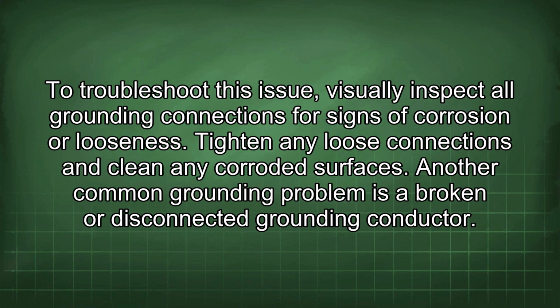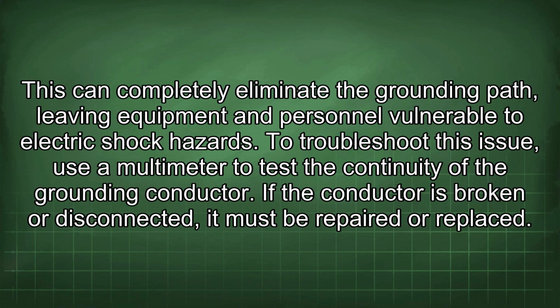Another common grounding problem is a broken or disconnected grounding conductor. This can completely eliminate the grounding path, leaving equipment and personnel vulnerable to electric shock hazards. To troubleshoot this issue, use a multimeter to test the continuity of the grounding conductor. If the conductor is broken or disconnected, it must be repaired or replaced.